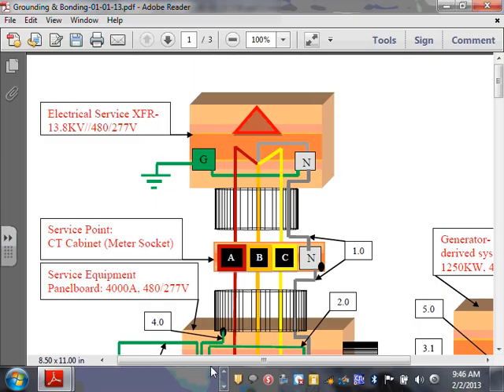So the engineers come over here and size a 4,000 amp switchgear. And with a 4,000 amp switchgear, you need 11 runs of 500 kcmil. That will get you there if you use 500. So take 11 sets of 3 phase conductors plus a derated neutral. Take them from here into the transformer. The problem when we go to the transformer, guys, is there are not enough lugs to land these 11 sets. Have you guys been there?